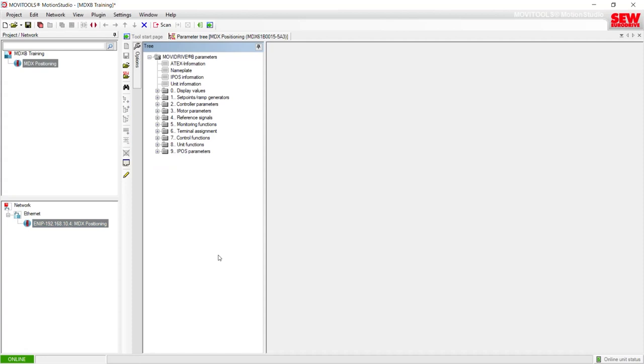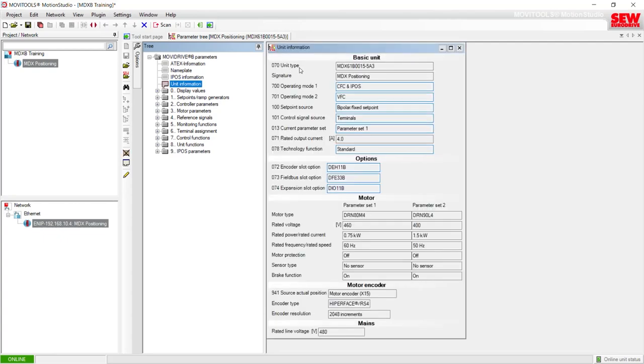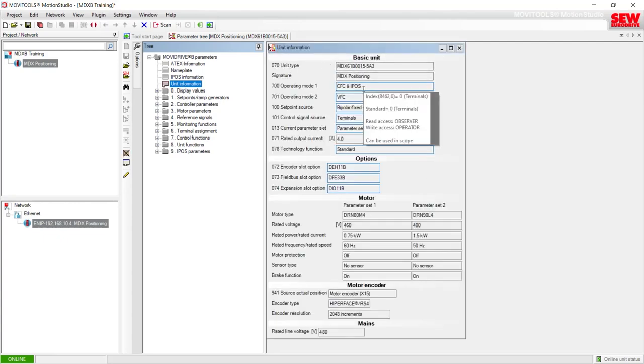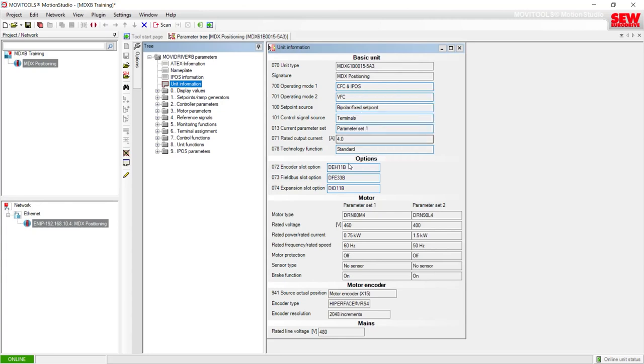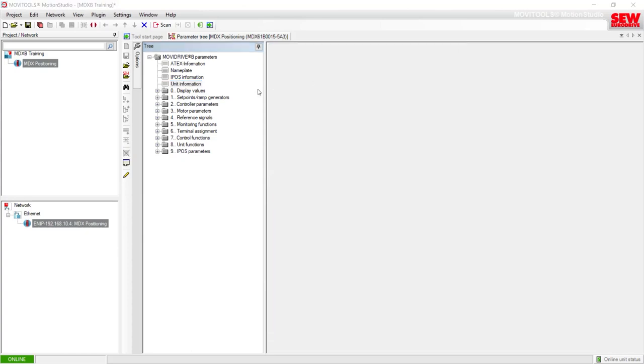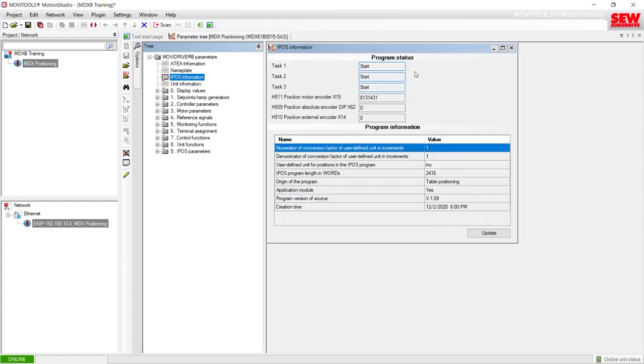You've seen the parameter tree in the previous exercise. The Unit Information tab is where you can look and see the model type of your MOVIDRIVE, its operating mode, whether it has any option cards installed and their model type, and the motor parameter set that is currently loaded. In the IPOS Information tab above, data will only appear if there is an IPOS program loaded. Currently I am using a Table Positioning IPOS program, which is an application module offered by SEW.